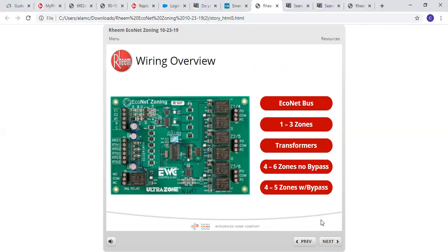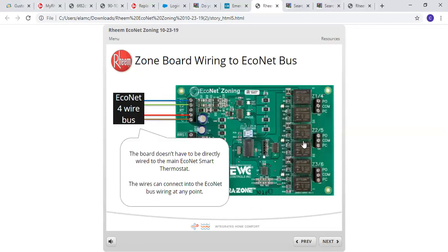So we're going to go over the wiring overview. The Econet bus, that's going to be your E1, E2, your R and C. Your E1 and E2 are going to be your communication wires. Your R and C are going to be your 24 volts. The board does not have to be wired directly to the main Econet stat. The wires can connect into the Econet bus wiring at any point. So this is going to be a little bit different than your traditional zoning, like Honeywell or Jackson Systems, what have you. It's going to be quite a bit different than that. But once you understand it, it's kind of plug and play, and it'll actually recognize itself.